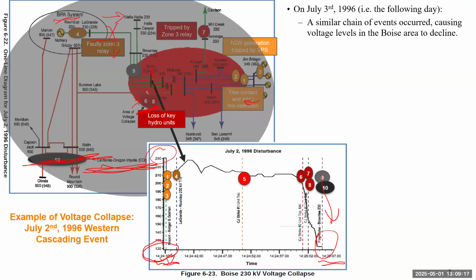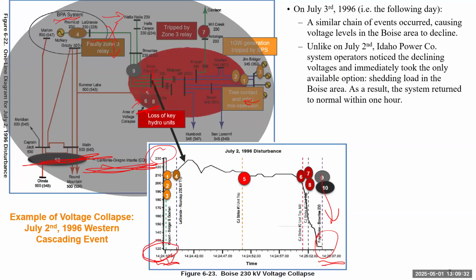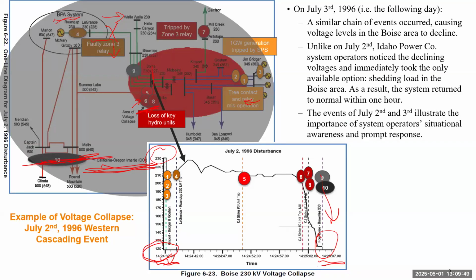Okay, so on the next day, which is July 3rd, a similar chain of events occurred, which caused voltage level in the same area to decline. But because the operator already learned the lessons from the previous day, so the power company is Idaho Power Company. So the system operator immediately took some action to shed load in this area, basically just disconnect some unimportant load. So that helped support voltage in this area. And the system recovered in just one hour.